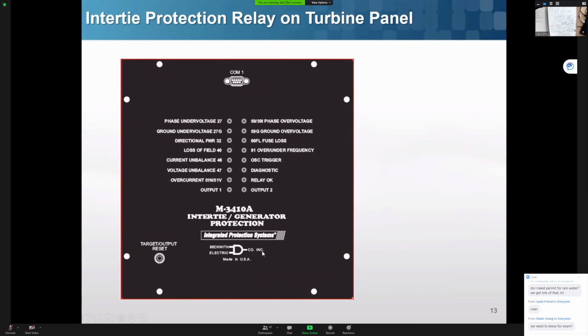You can see here, this is for the hydro connection down there. So they will have under voltage, unbalanced current, voltage unbalance. Yes, you need to know that. Or over or under frequency. They will have a bunch of lights or monitors or alarm signals if any of those things happens.